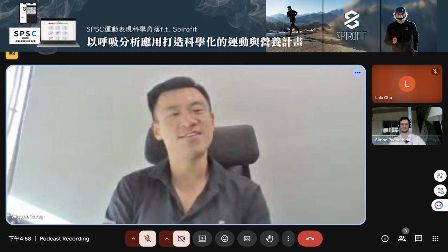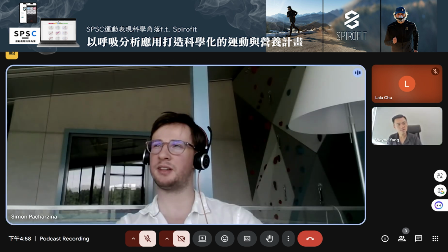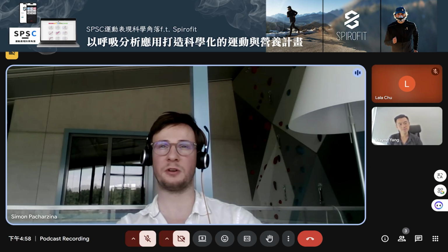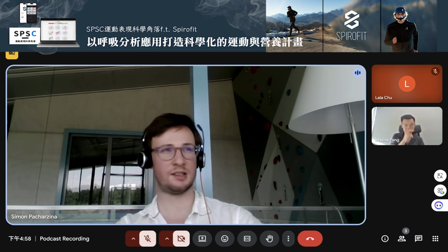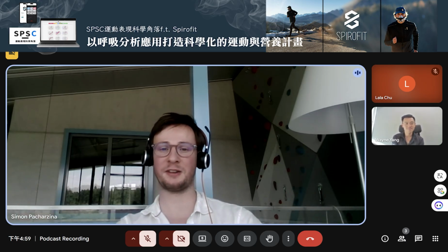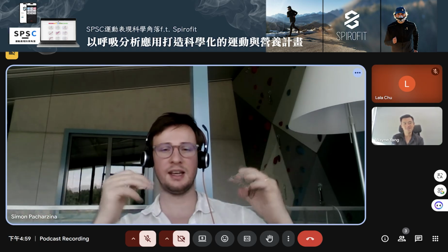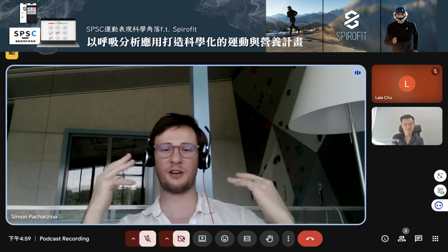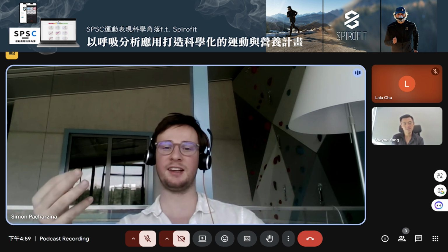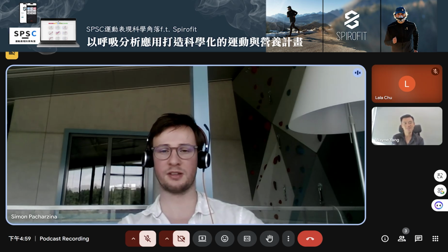Yeah. Okay, perfect. And what about the dynamic testing limitations? For dynamic testing, we have some limitations concerning temperature. We did go to 0 degrees and did measurements that looked all right. We just don't have the capacity to do real studies on how low we can go. But at a certain point, the gas in the chamber is so different from what you're exhaling and inhaling that it starts to offset the measurement.